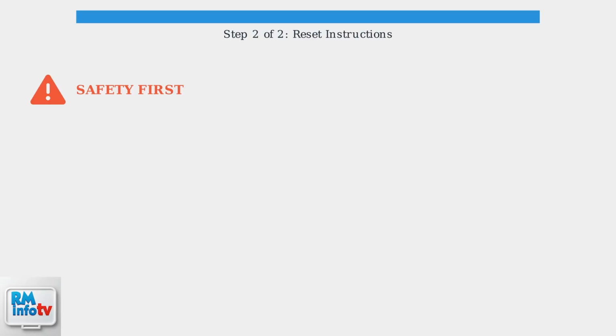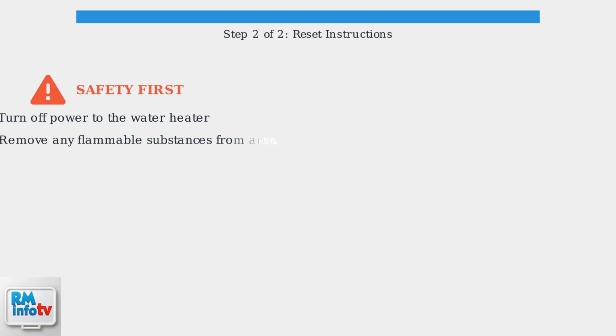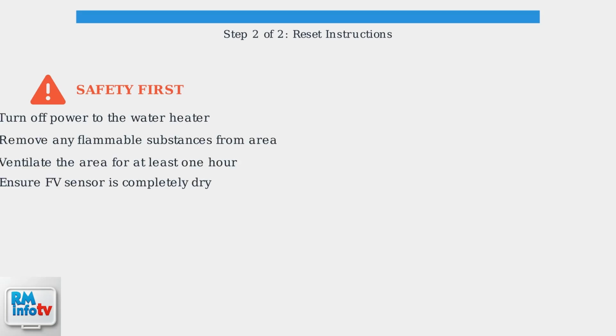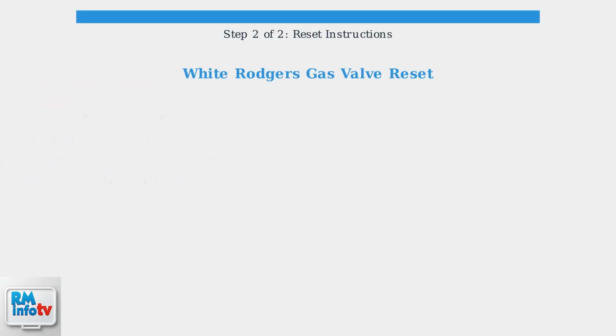These steps must be completed first to prevent dangerous situations. First, turn off power to the water heater. Remove any flammable substances like gasoline, paint, or cleaning chemicals from the area. Ventilate the space for at least 1 hour and make sure the sensor is completely dry before proceeding. Now we'll cover the reset procedures for the most common gas valve types.